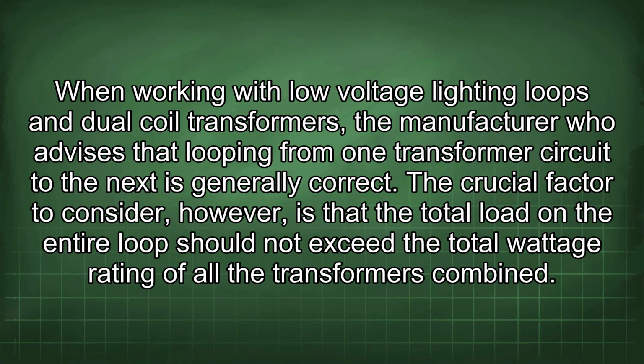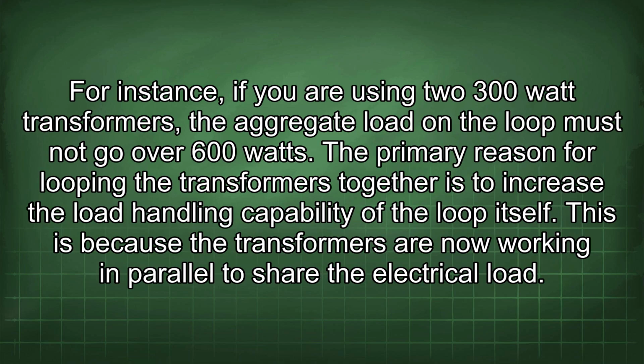When working with low-voltage lighting loops and dual-coil transformers, the manufacturer advises that looping from one transformer circuit to the next is generally correct. The crucial factor to consider, however, is that the total load on the entire loop should not exceed the total wattage rating of all the transformers combined.